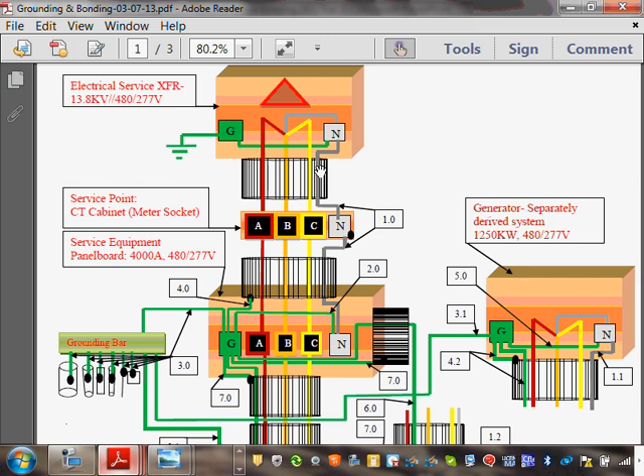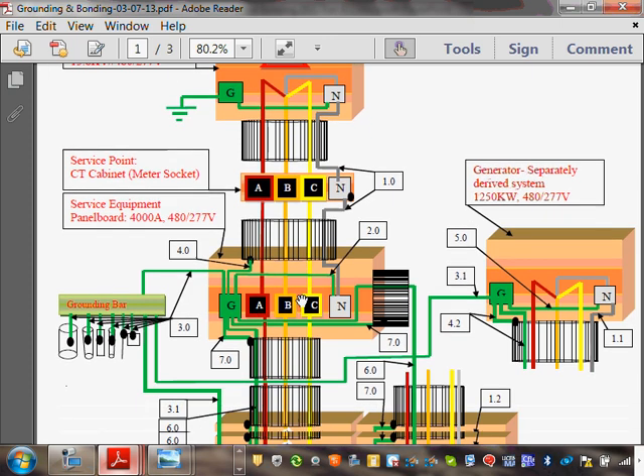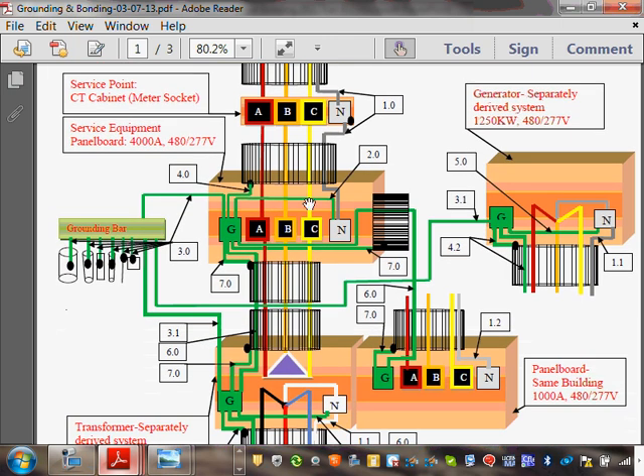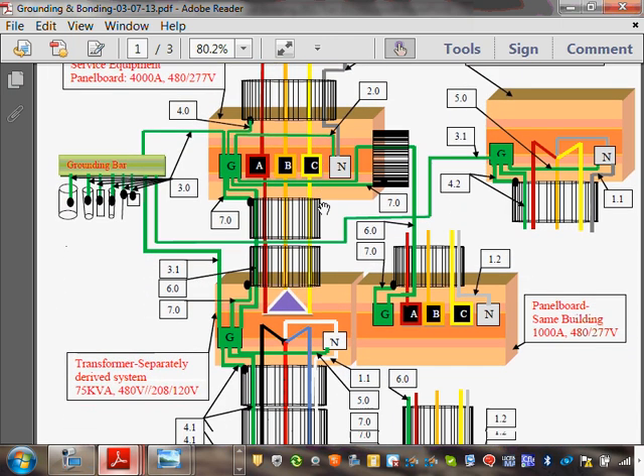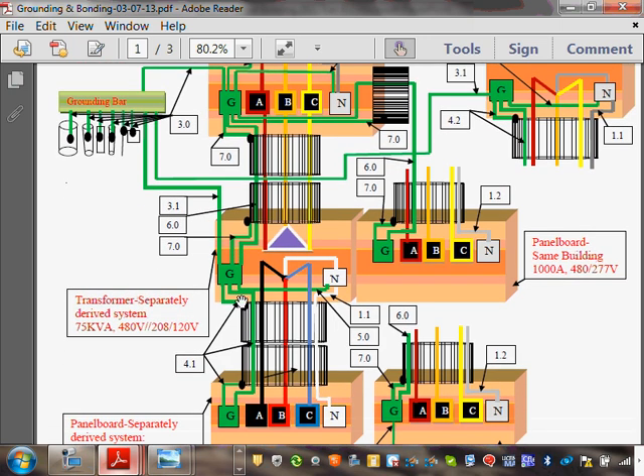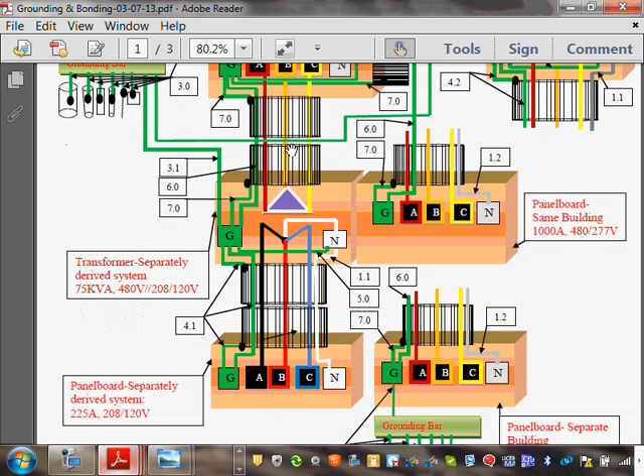Now, change this 4,000 amp into 100 amp, 120/240, and you're dealing with your house. Really, nothing will change. So being big amps doesn't mean anything. All the stuff will apply for big amps or smaller amps, big voltages or smaller voltages, as long as you're 600 volts or less. So here's my transformer grounded. Then I brought the power through a meter or a CT cabinet into my first panel. And that's where I'm going to do grounding and bonding at the service. That's what we call the service. And then from the service, I took multiple feeders. And right underneath it, I feed a transformer that feeds a 208/120 panel. Can you guys see that? That will give you a separately derived system.